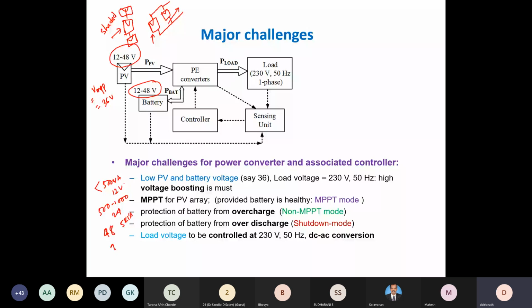Commercially available lead acid batteries for home appliances are generally used because they are cheaper, and they come in a 12 volt packing. So if you want to increase the battery voltage, you have to connect several of them in series, and then charge equalization problems come up. To avoid that, you can do it with some precaution, but otherwise for a very low power system, you can use a 12 volt battery. Most commercial inverters from Microtek, Su-Kam, Luminous, all generally use 12 volt batteries for home inverters.